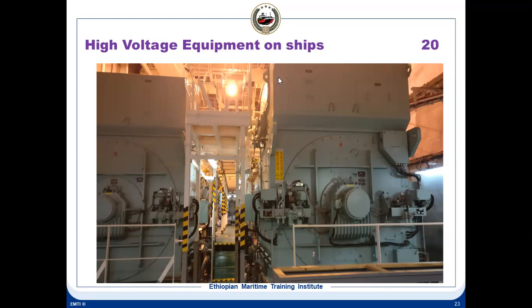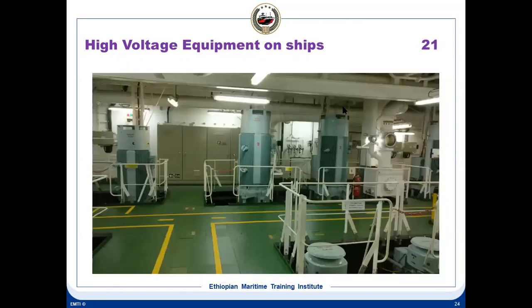This is the alternator part. On top you can see an air cooler which is cooling the alternator, because the air which is coming is passing through this air cooler and blowing through, and it is used for winding cooling. It's a water cooled generator. These are the ballast pumps, high voltage ballast pumps. You can see here number 2, number 3, number 1. These are the high voltage ballast pumps which use 6600 volts.